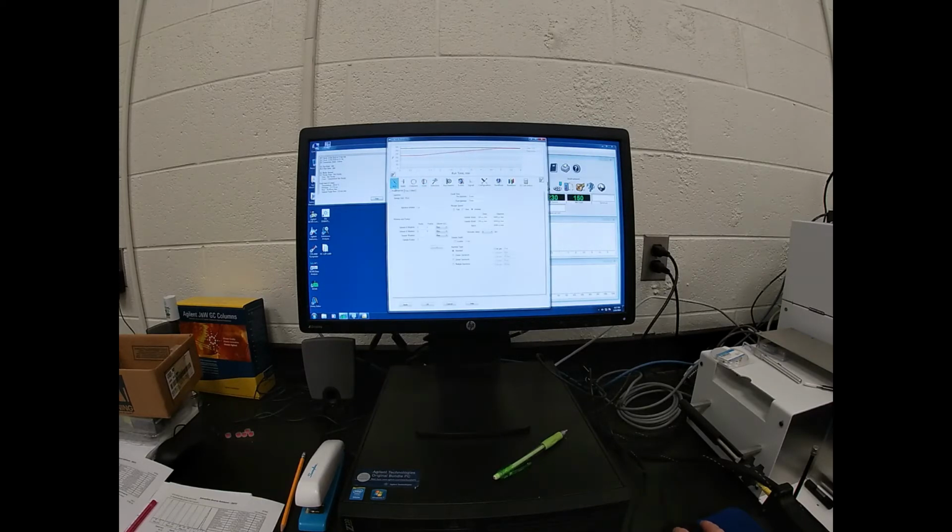It's giving us a little bit of information, and now we actually end up here where we're interested. This is our autosampler, so we program our autosampler here. We select an injection volume. And then we can have washes and pumps. So this has to do with how many times we want to wash in a solvent. We can wash in the sample, then pump the sample and inject, and then a post-injection wash as well. We have a standard injection. You can also do layered injections to try and improve your efficiency.